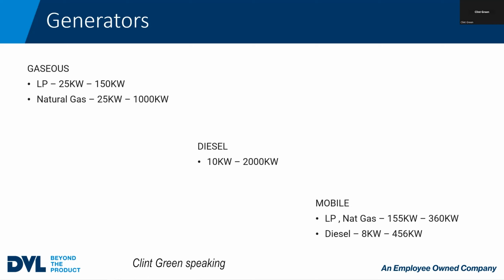If you're backing up the entire facility, then we need to think about, okay, can I get away with, say, 1,000 kW natural gas? Now we have to take into account elevation. 1,000 kW at our elevation, for instance, you're going to get maybe about 900 kW.